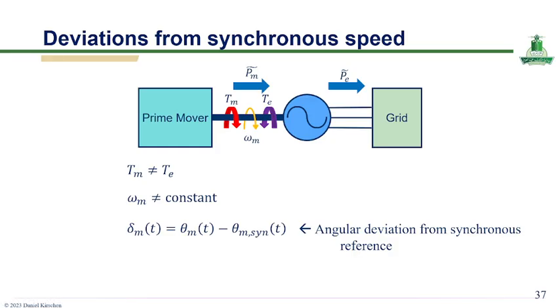When the mechanical torque Tm is not equal to the electrical torque Te, the generator no longer operates in steady state. In this case, the rotor speed is no longer constant, meaning omega m is not equal to a constant, and the system experiences dynamic changes. To analyze this behavior, we define the angular deviation from synchronous speed as delta m(t) equal to theta m(t) minus theta m synchronous. This quantity represents how far the rotor angle has deviated from the synchronously rotating reference frame. It is a key variable in stability studies as it describes the dynamic response of the generator during and after disturbances.